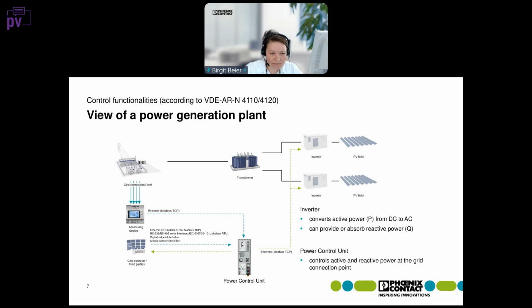The most important one is the connection to the grid operator via telecontrol. You can use many different ways to connect to the grid operator, for example Ethernet via 104 protocol, Modbus TCP, or a serial interface, digital setpoint definition, or analog setpoint definition. Then the inverters, in this case, have an interface via Ethernet, Modbus TCP. And last but not least, there is a measuring device, the energy meter, which is very important to give feedback from the grid connection point and is measuring all the parameters. It is connected via Ethernet with the Modbus TCP protocol.